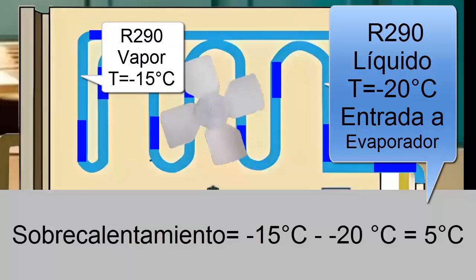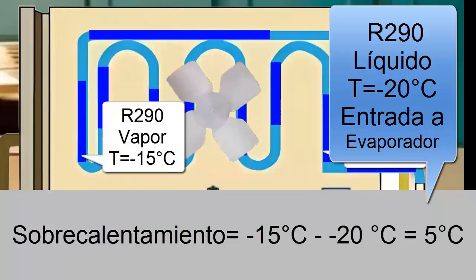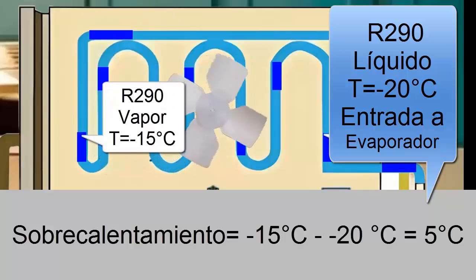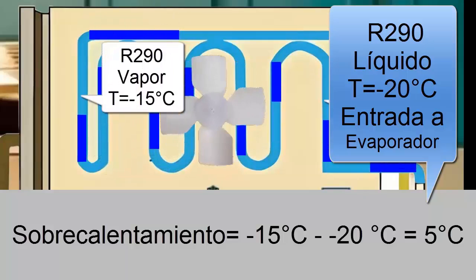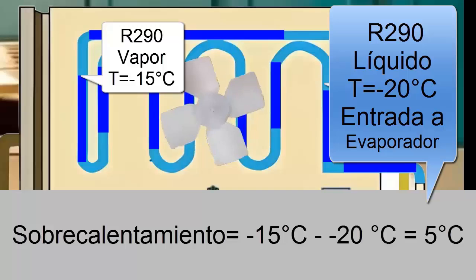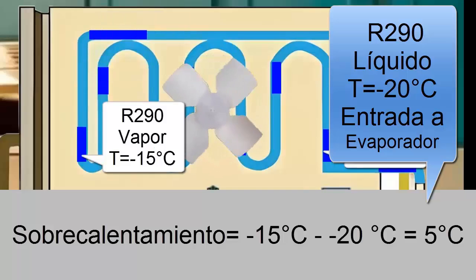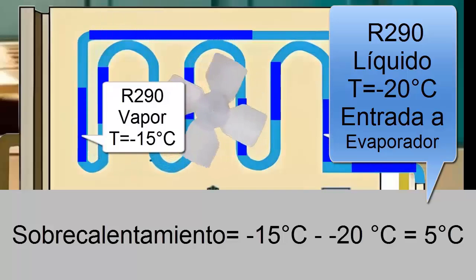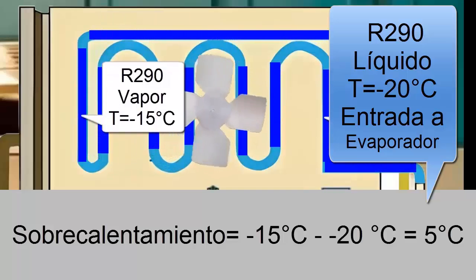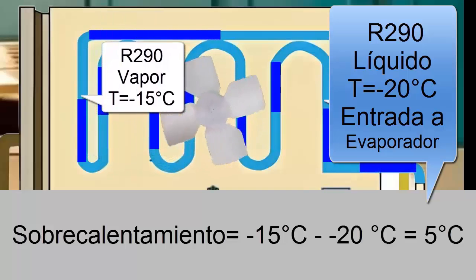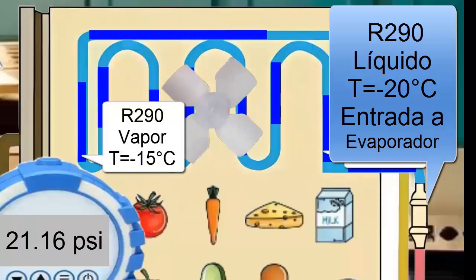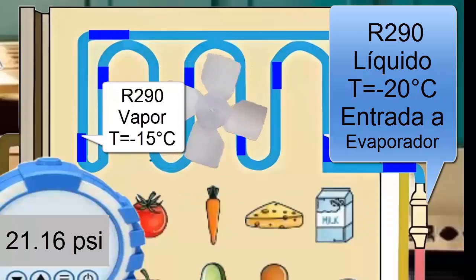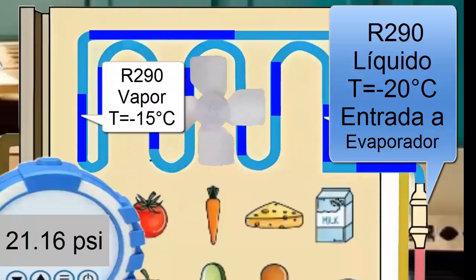Although the temperature undergoes a slight change, the same does not happen with the pressure, and we can approximate and say that the pressure of the R290 at the evaporator's exit is practically the same — it still amounts to 21 pounds per square inch.